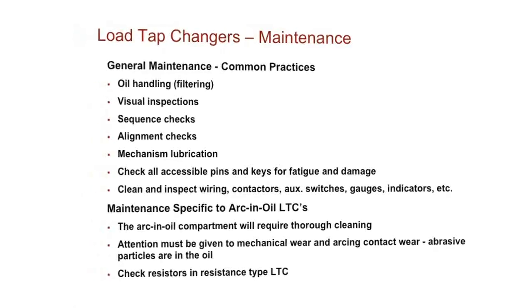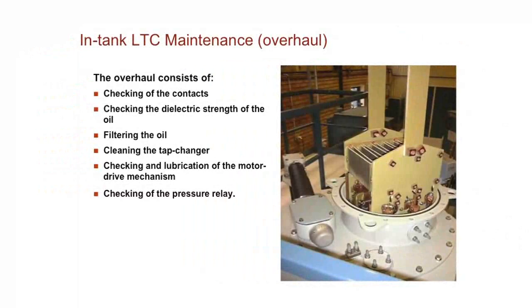We're talking about the motor drive. Talking about cleaning and inspecting the wiring and the contactors, auxiliary switches. These are all in your motor drive cabinet, where these components are located. But it's a good time to check them all and make sure that you don't have any oxidation going on on your contacts, no loose wiring or frayed wiring since it's been operating. Obviously, on the side of a transformer, it's going to receive some vibration, so things do have a tendency to loosen up or move over time.